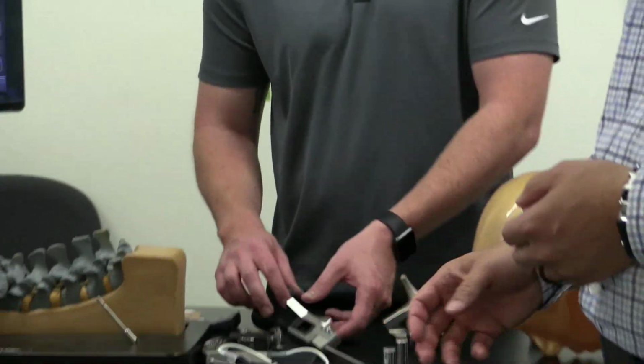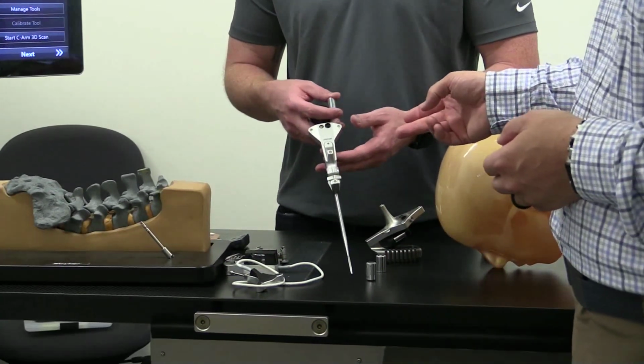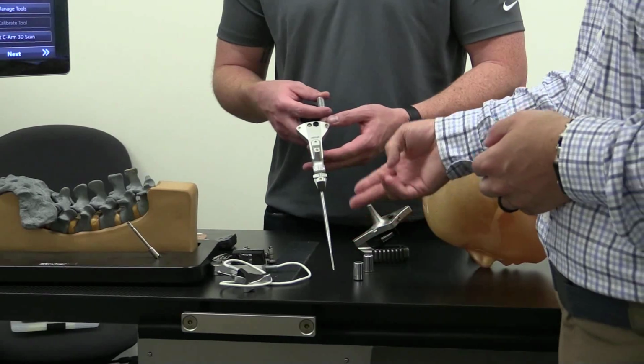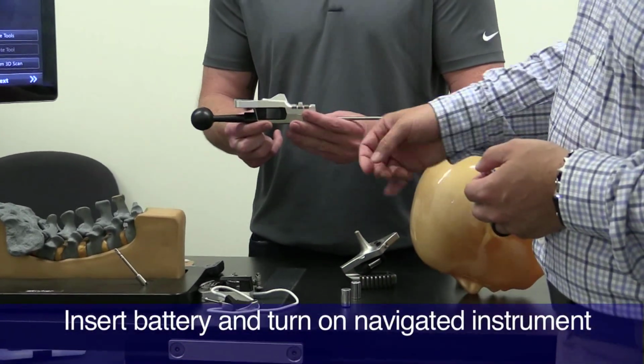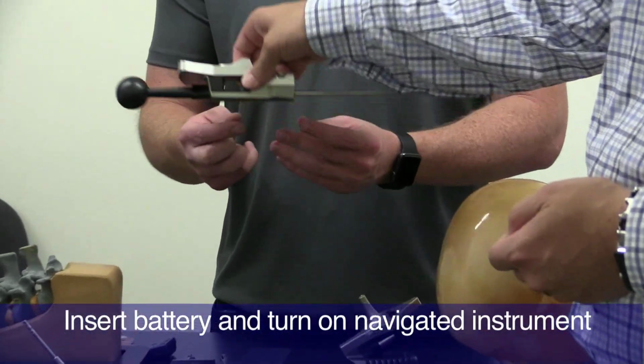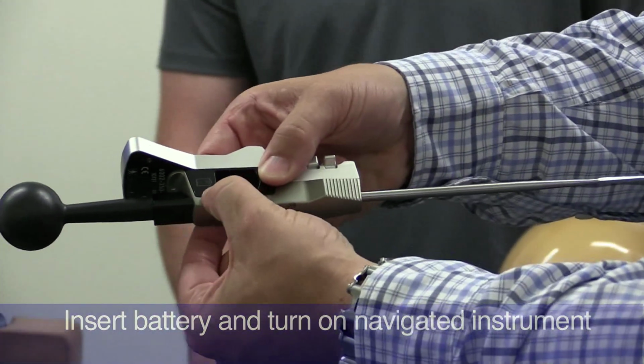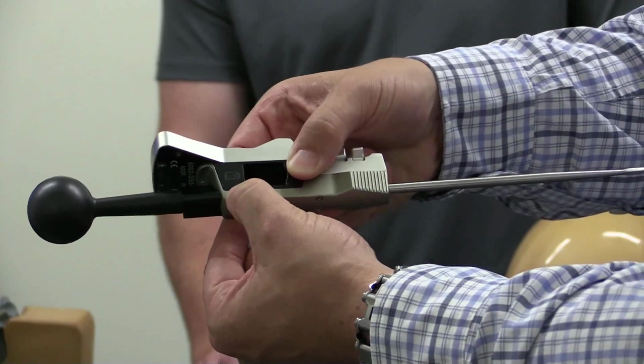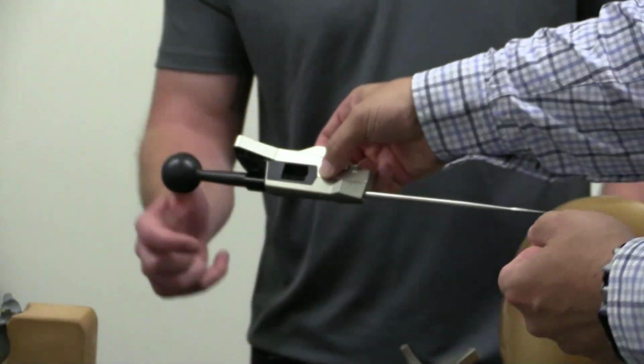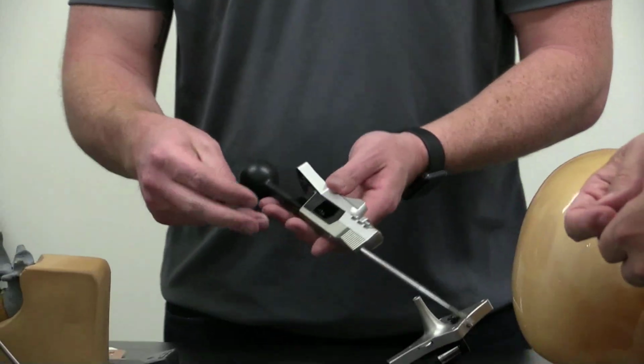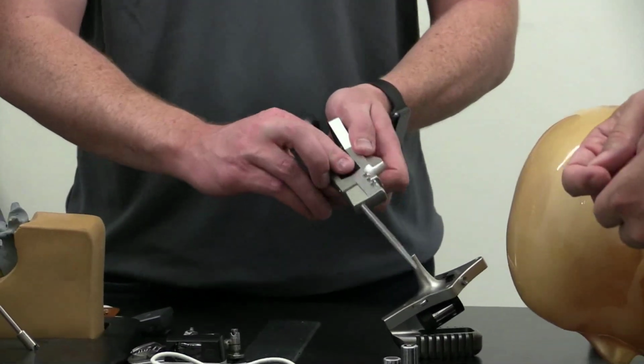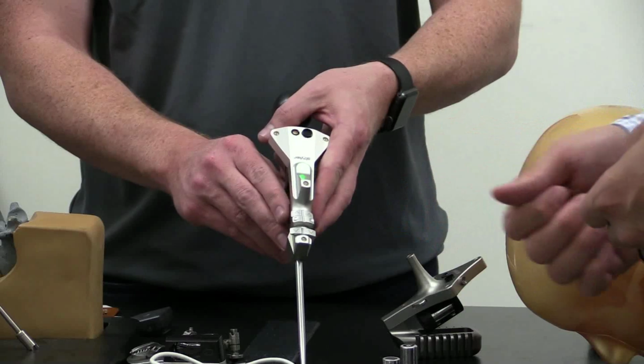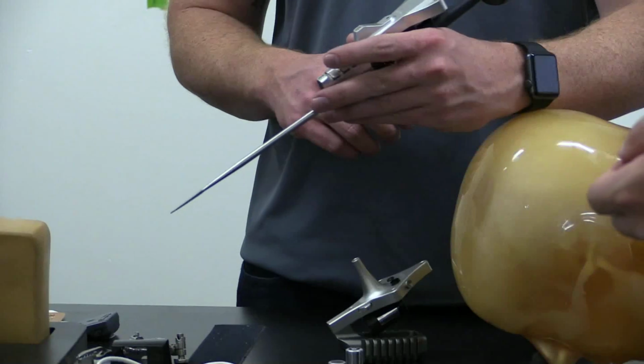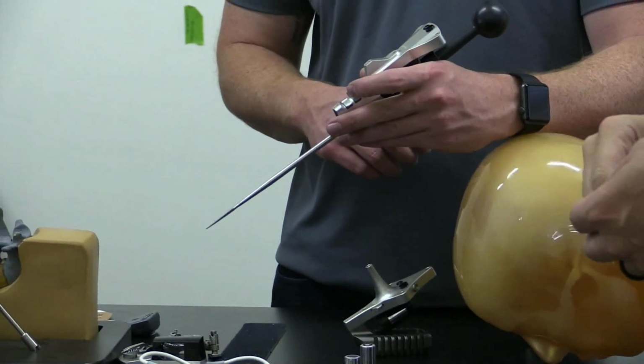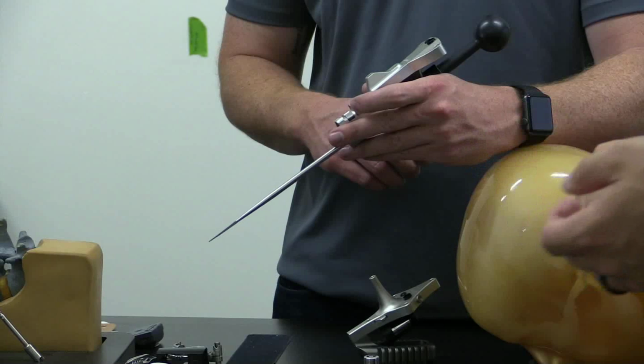The next thing we'll do is turn on one of the navigated instruments. In this case, it's just a thoracic pointer or a gear shift. Same rule: it shows here with a plus and minus sign which direction the battery goes on the inside. Again, the flat of the battery goes onto the spring. It will engage, and then the light comes on, and then goes off, which says everything's okay. In this case, the LEDs are pointing towards the localizer. You're going to press and hold the enter button for approximately 2 to 3 seconds.